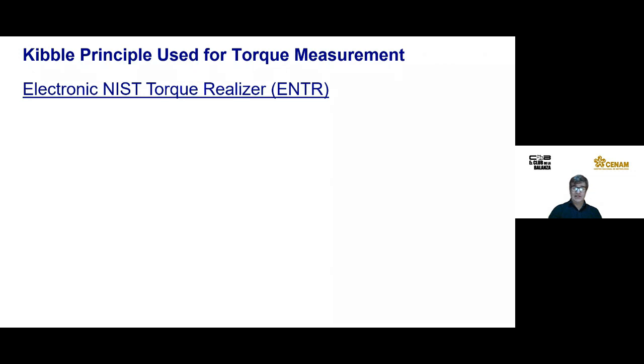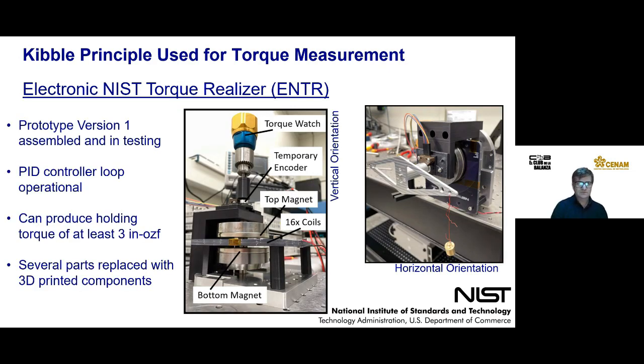This is really interesting, because not only can you measure mass with a kibble balance, you can measure force, but you can also measure torque, because you can generate a rotational force rather than a linear force. So NIST have this electronic torque realizer — essentially kibble balance principles used to produce a torque, which can be used to calibrate torque transducers, torque wrenches, and primary torque standards.